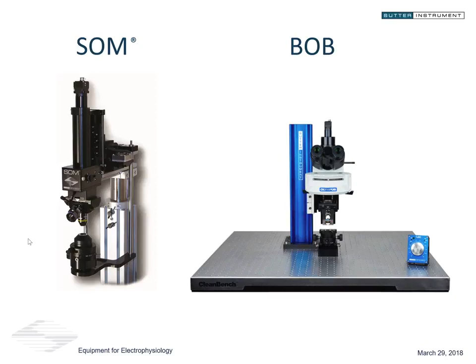If you want to use the same rig to record from both tissue slices, brain slices, or slices from other tissue, and dissociated cells, cultured cells, adherent cells, then you definitely want to use an upright microscope if you don't have the option to use an upright microscope on one rig and an inverted microscope on the other rig. You need water immersion objectives, obviously, with certain limitations, but it definitely is possible to use that on an upright microscope, including the SOM and the Bob. What you cannot do is record slices on an inverted microscope, because you would have to, in essence, focus through the entire tissue, and that degrades the image quality to a point where it's tricky, to say the least. It has been done, but I wouldn't do that.